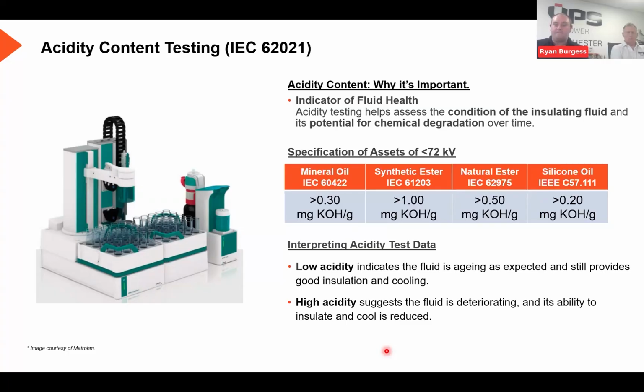It's a time factor. And the impact is obviously that it's going to deteriorate your insulation. The paper insulation, typically on your windings, will start deteriorating and ultimately result in a failure if it's not addressed in a quick enough time. But again, similar mitigations: resample, make sure that it is from the sample. You can monitor if it's in low amounts initially, monitor until it increases, but then you can start looking at things like possibly changing the oil out or recirculating the oil to a suitable condition. There are mitigations out there, but again, it's important to have that whole picture before you choose what mitigation strategy you're going to use.